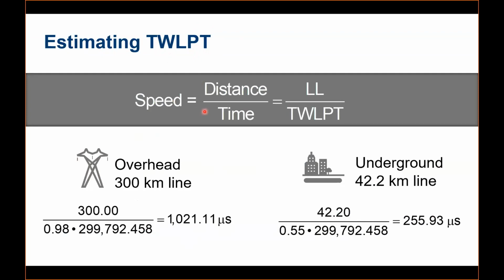There is a way to estimate or calculate that, because these traveling waves are electromagnetic waves, and we can compare them with the speed of light. For overhead lines, the characteristic speed is 98% of the speed of light. They are very, very fast. You can just consider that they travel at the speed of light in overhead lines. And for underground cables, the speed is much slower compared to overhead lines because of the properties of the insulation and the cable. It's 55% of the speed of light.